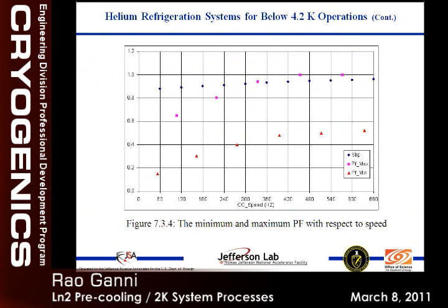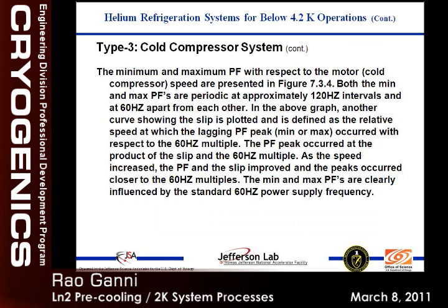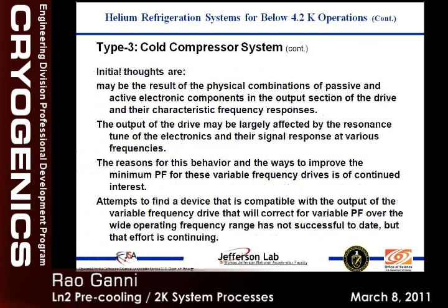So if you look at this, this is how the power factor average was maintained. The minimum was like this, the maximum was like this, so you can come up with the speed ratios where you don't hit these minimums on more than one at a time.